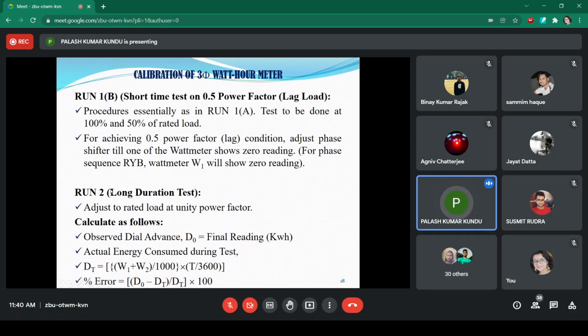Run 2 is a long duration test. Here 30 minutes are allowed. Before the start of the experiment, the energy meter reading should be noted down. That is the initial reading. After completion of the 30 minutes, the energy meter dial reading should be noted down. Taking the difference, final reading minus initial reading, the energy consumption in kilowatt hours should be calculated.